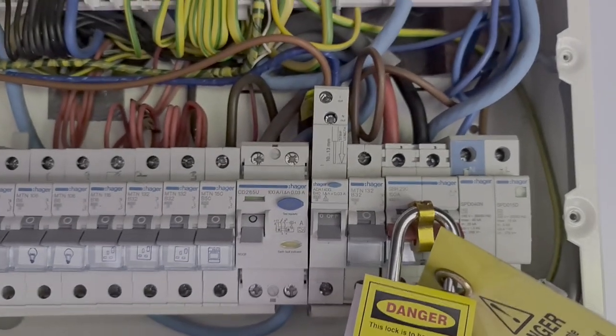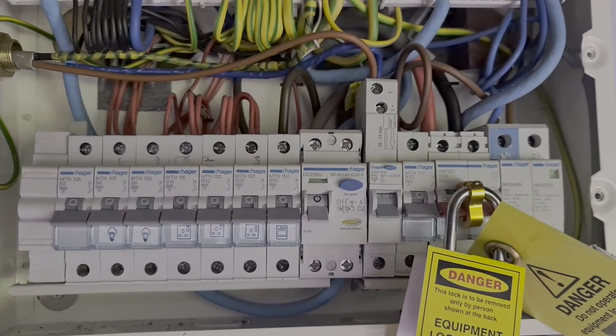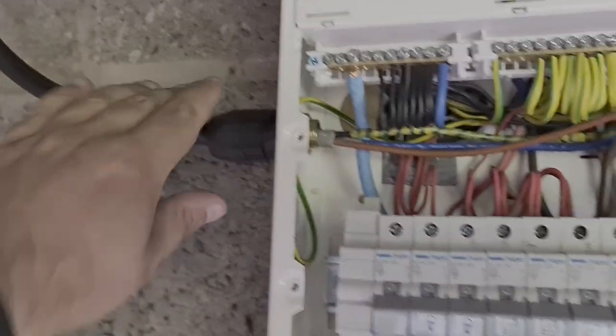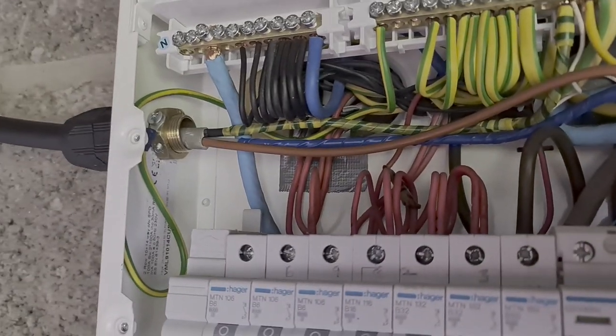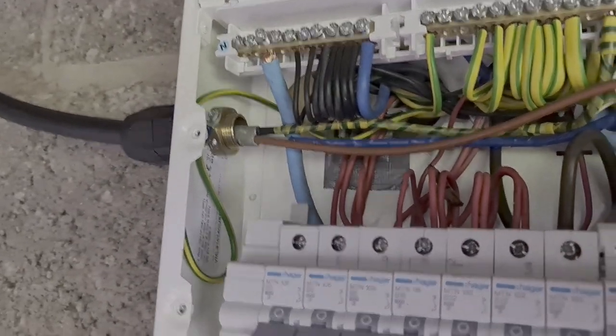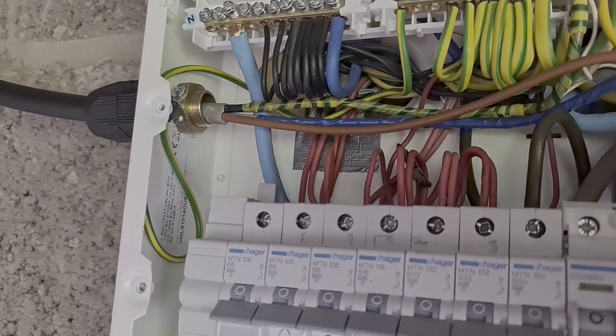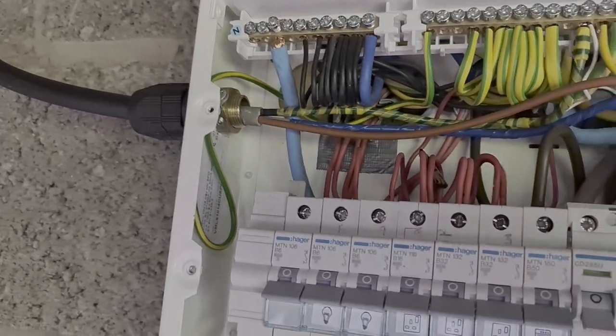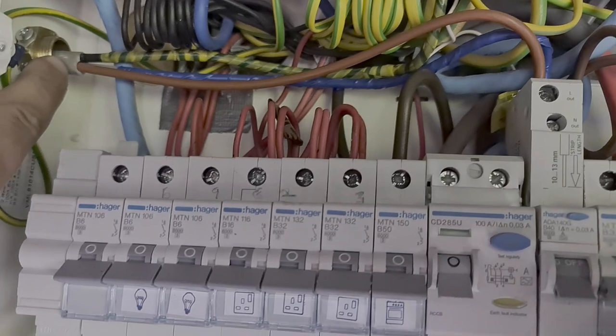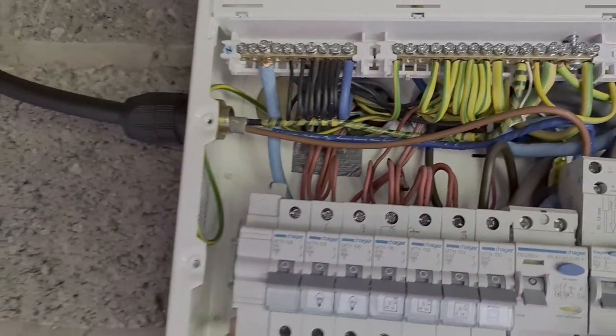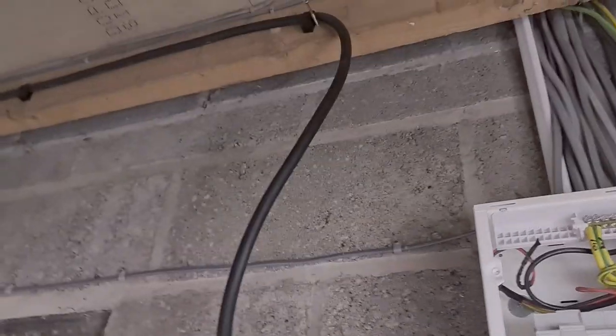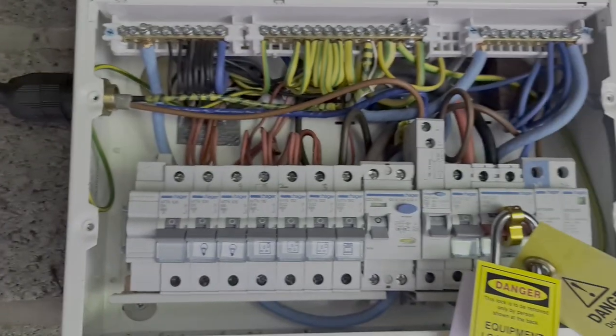So we've gone for an RCBO in there, it's type A, and you can see we've dropped it in before the RCD protected circuits. We dropped the steel wire armour in and glanded it in the side, so we've got one of the piranha nuts on the SWA gland, and we've put the grip screw in and an earth fly lead as well, also with teeth biting into the case, so that's extra well earthed. We just need to tidy up this little bit here, get on with that in a sec.